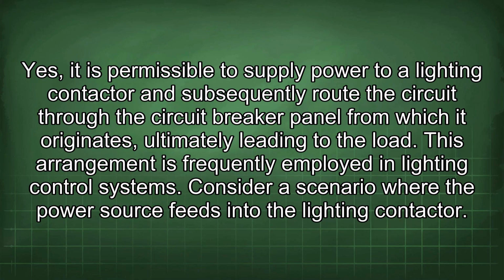Yes, it is permissible to supply power to a lighting contactor and subsequently route the circuit through the circuit breaker panel from which it originates, ultimately leading to the load. This arrangement is frequently employed in lighting control systems. Consider a scenario where the power source feeds into the lighting contactor.